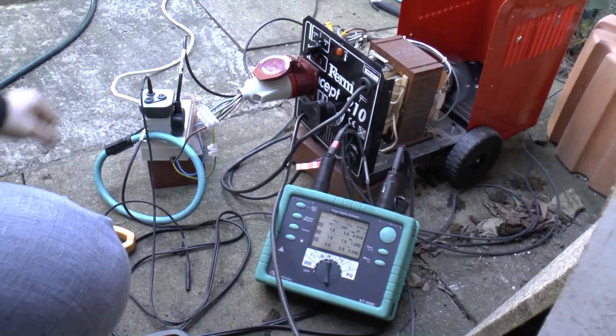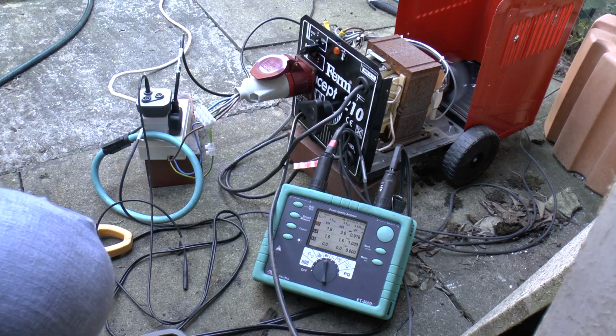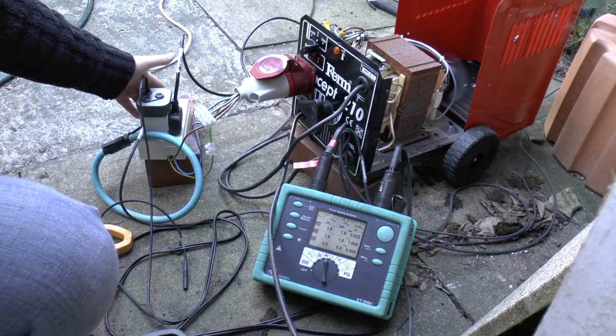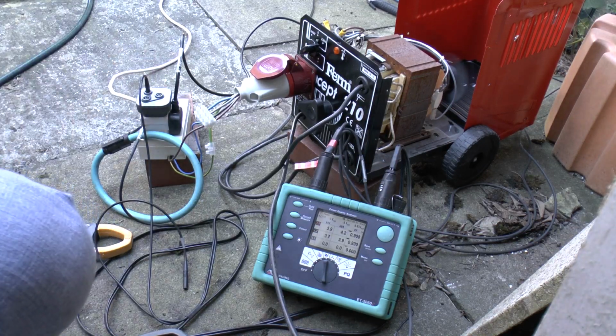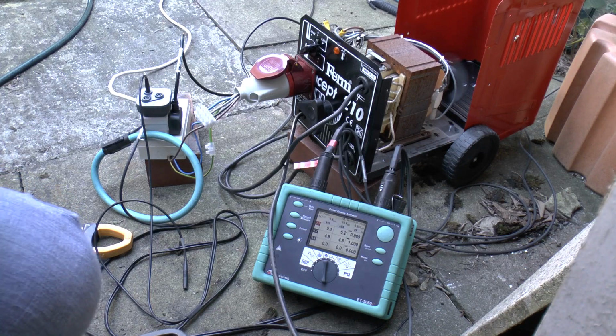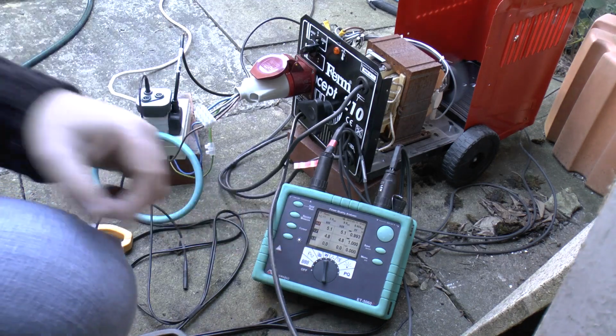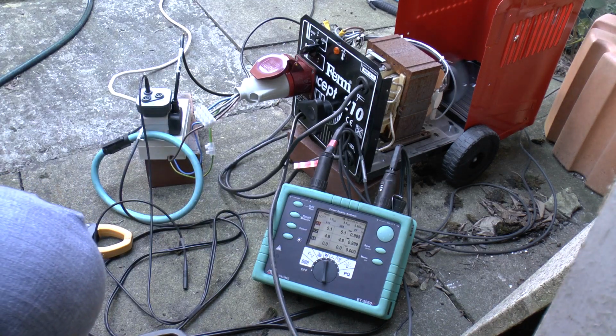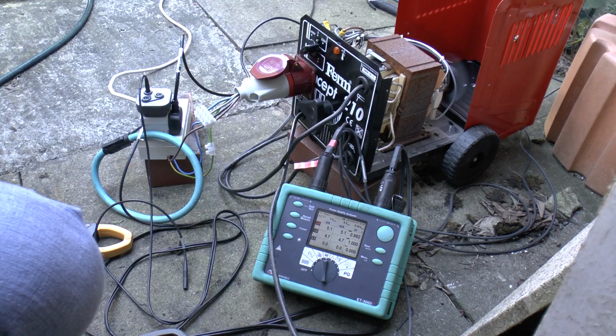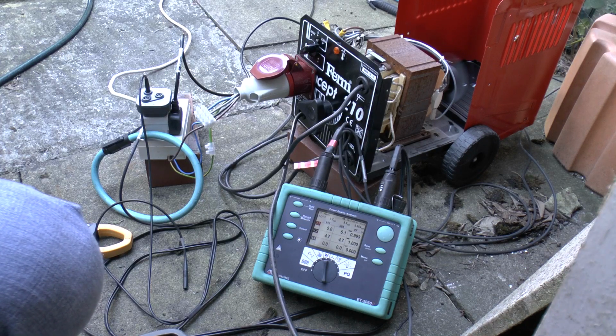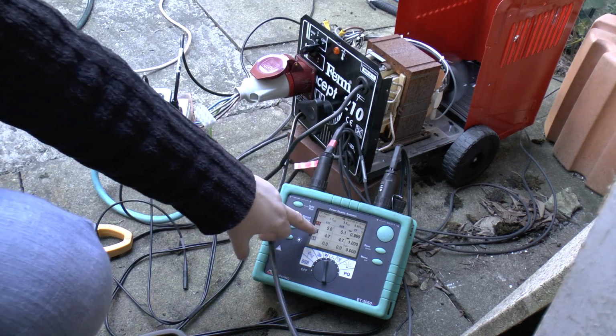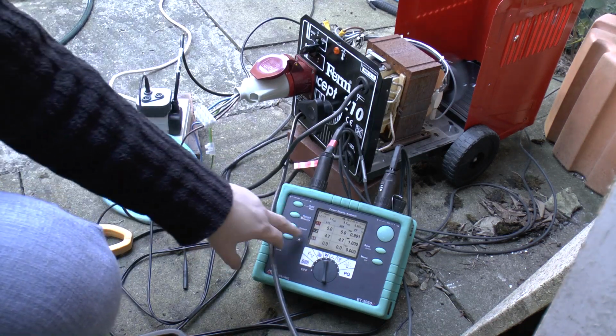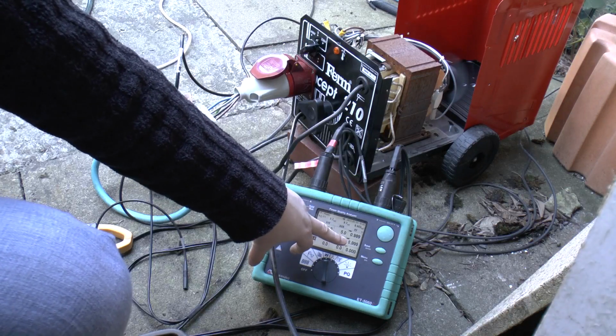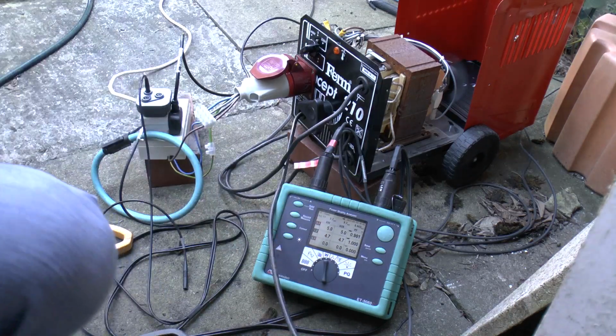Now then, what will happen when I add those two 2.5 kilowatt fan heaters on? See, the input current has now jumped up to 5.1 kilowatts. Now they're not going to draw 5 kilowatts a piece because they're not running at 240 volts a piece. They're running at around about the 200 volts mark. We'll take a look in a second. And the output, 4.7 kilowatts, 4.7 kVA. Again, they're a resistive load, so the power factor is unity.